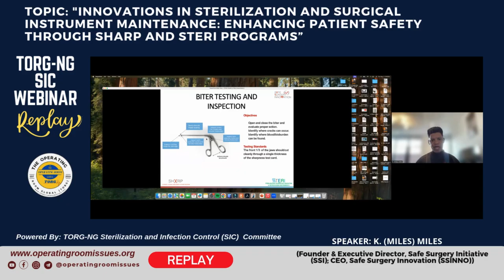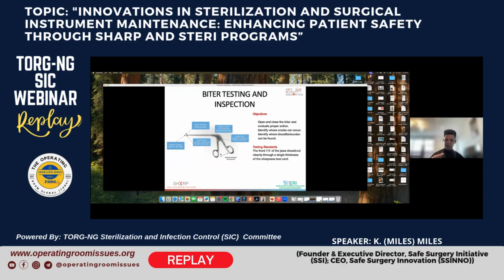Same thing with the biters. This could be an ortho punch, it could be a biter, it could be called by a lot of different names, but the inspection points are pretty much the same regardless of the type of instrument. Once again, you want to look at those distal tips, checking the jaws, making sure they're meeting evenly, inspecting the cutting edges, and then inspecting both sides for cracks. And also always making sure that when you open and close that instrument, it's opening and closing properly.